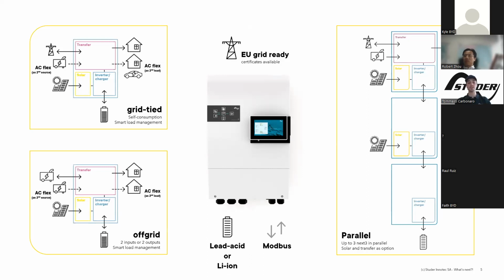There's also the parallel possibility, so you can install more devices in parallel if you need more power. Studer has designed this device from its experience with a modular design, because sometimes in a parallel solution you only need the solar or only the inverter charger function. So the design inside the next3 is modular. You can choose the module you want when upgrading your installation. This is the result of more than 30 years of experience in this domain.